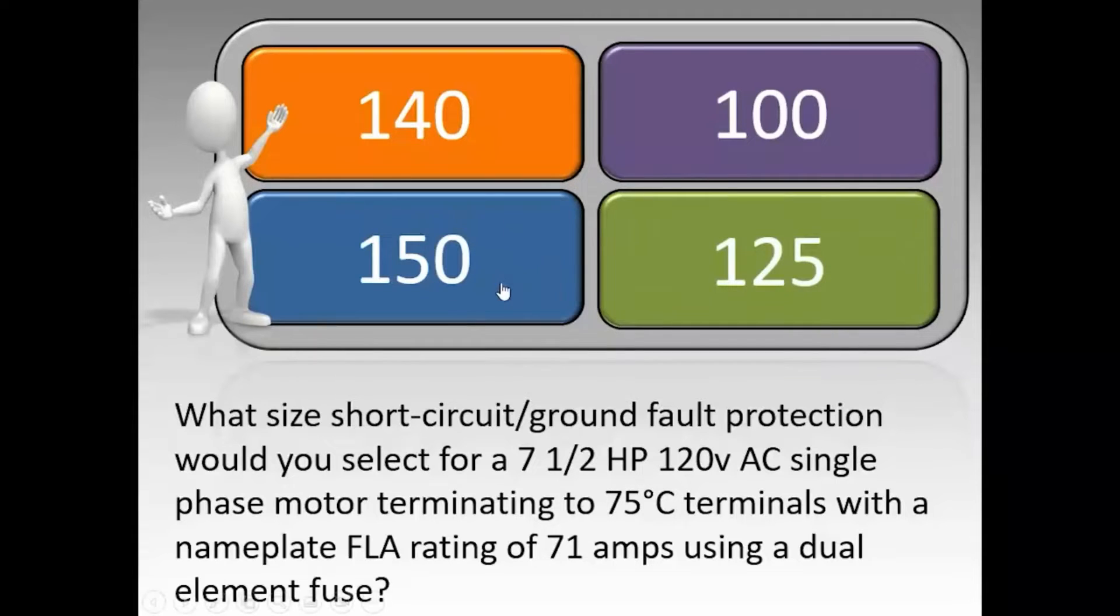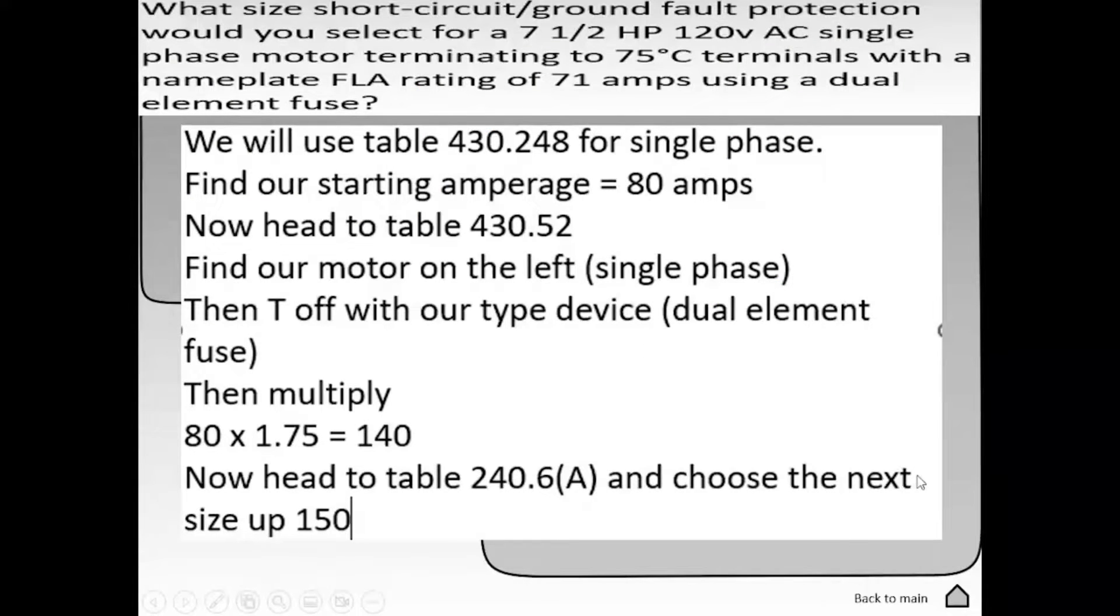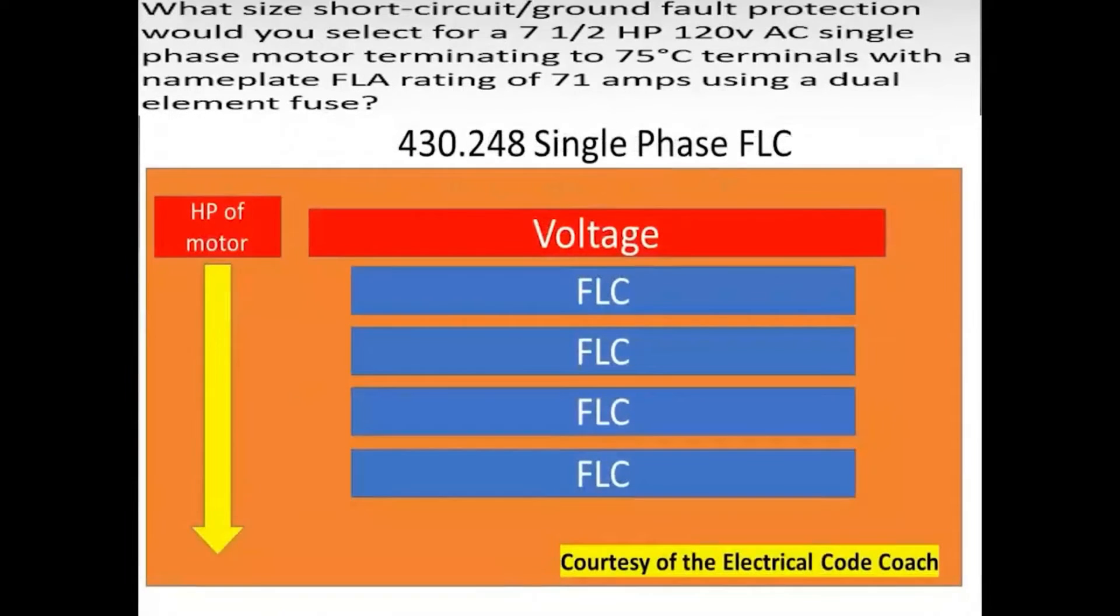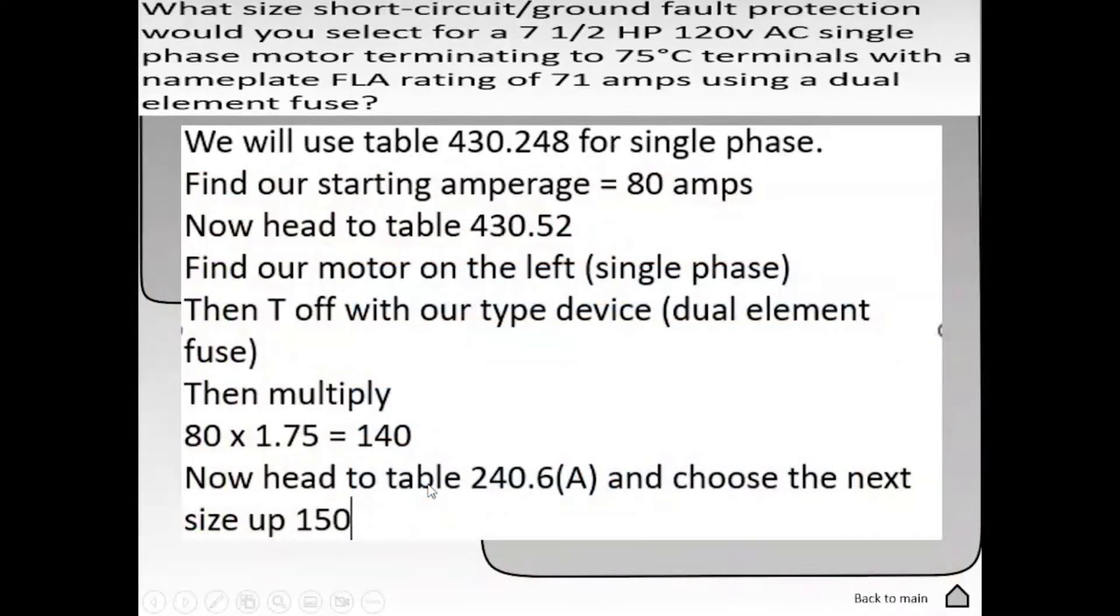The correct answer is 150. For this one we're going to be using table 430.248 for single phase and we're going to find our FLC. We start on the left hand side and find our horsepower, then come down and tee off with our respective voltage and we will find our FLC which in this case is 80 amps.